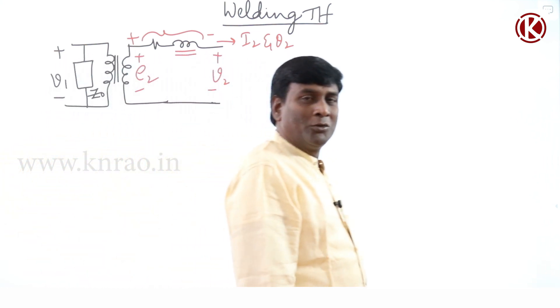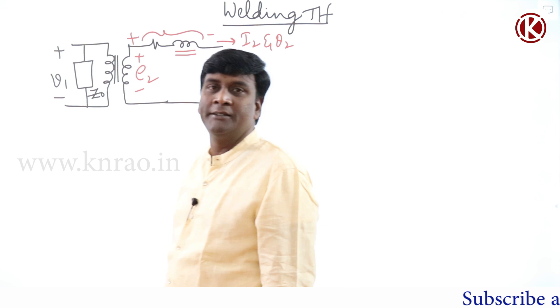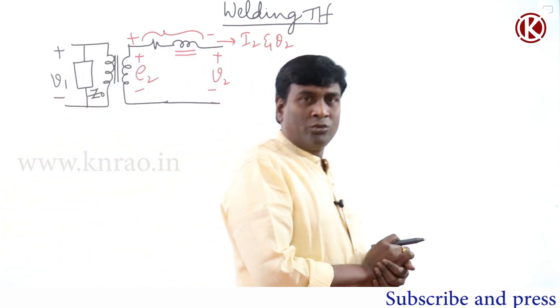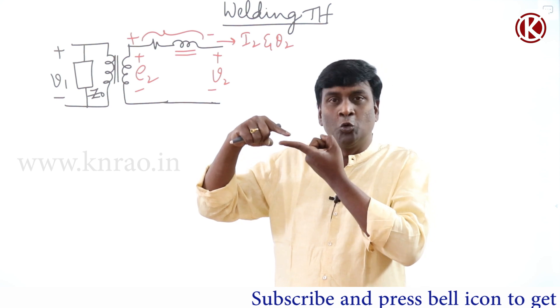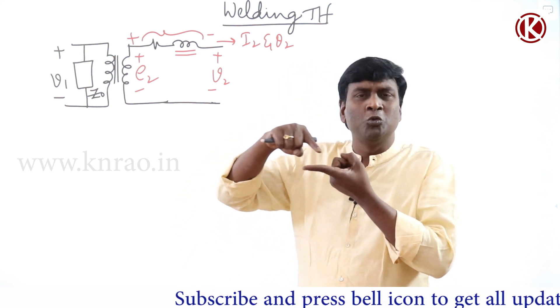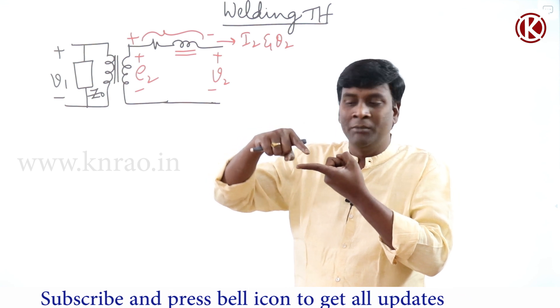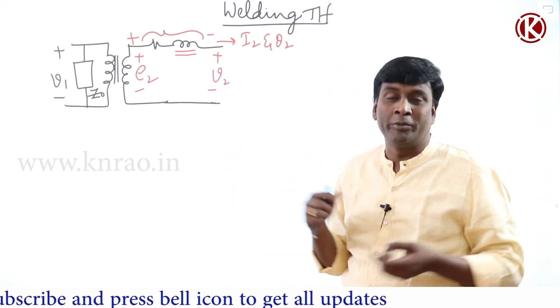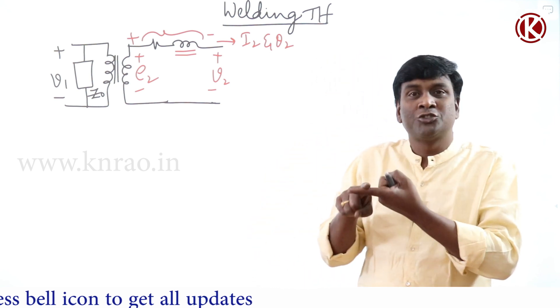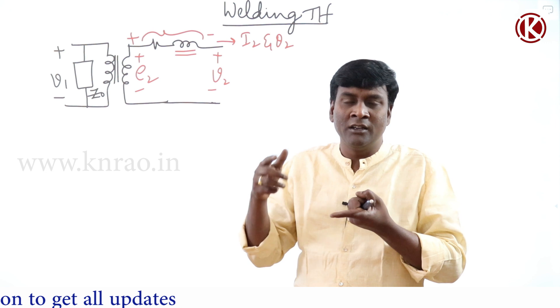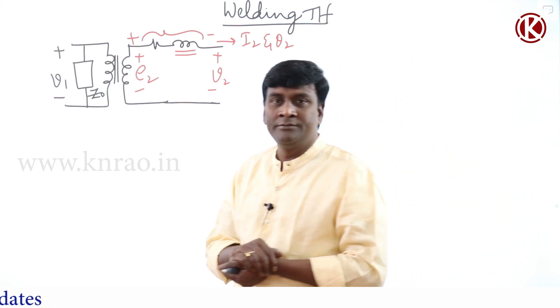From a voltage regulation point of view, leakage should be less. But in some applications leakage may have to be tremendously high — for example, in a welding transformer. In welding, a two to three mm gap must be maintained between the electrodes. No operator can maintain that gap precisely; it will repeatedly short circuit and open circuit, so the welding transformer must be designed to handle short circuit conditions.